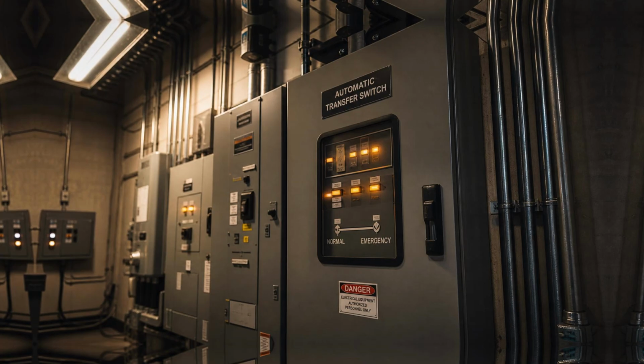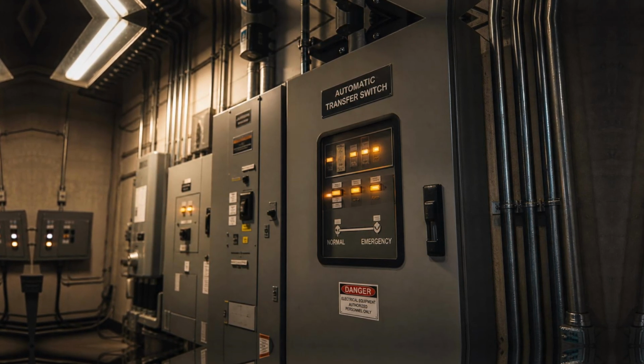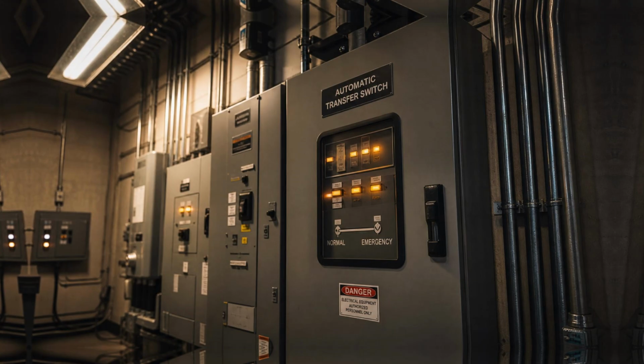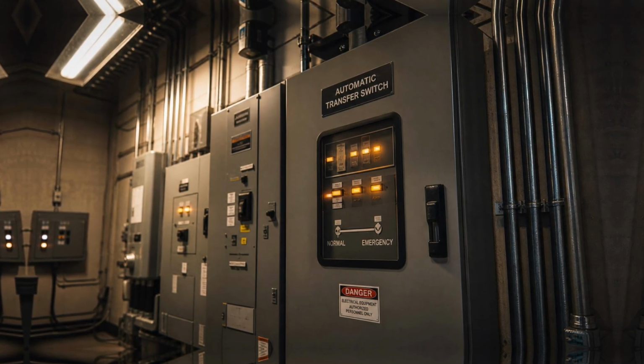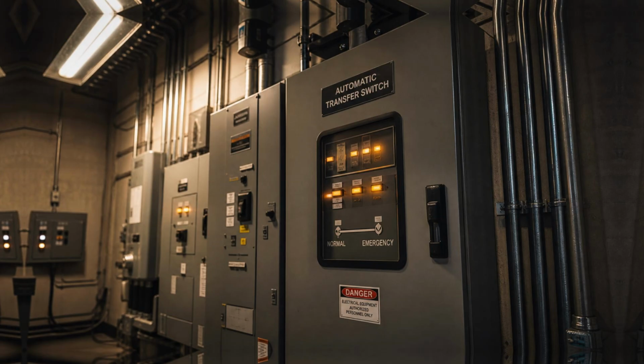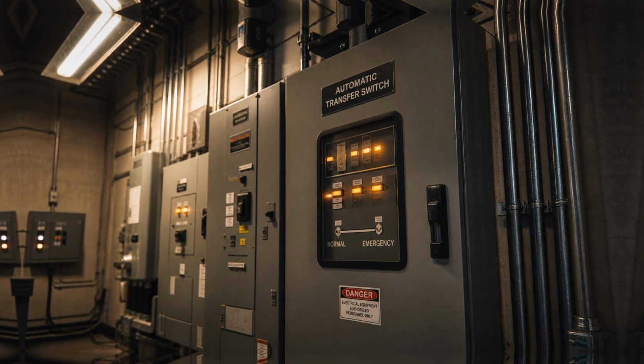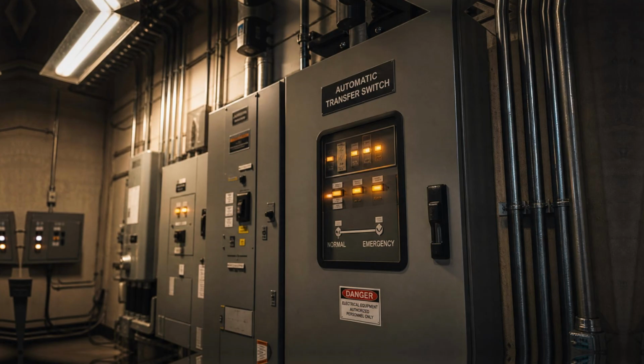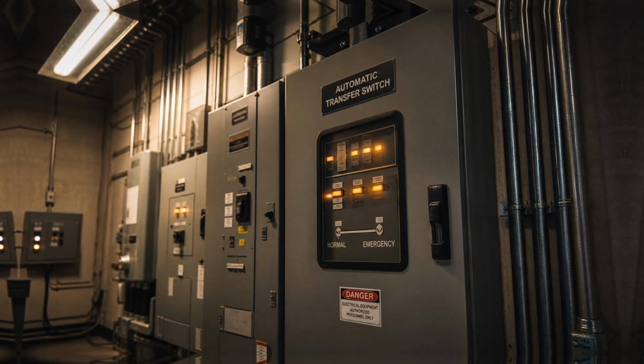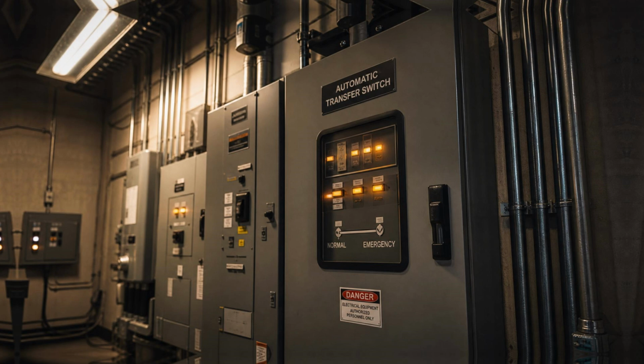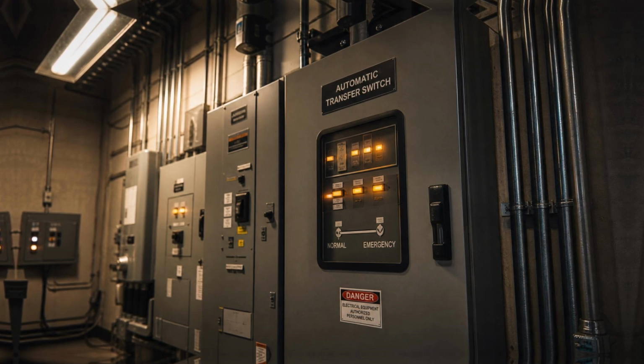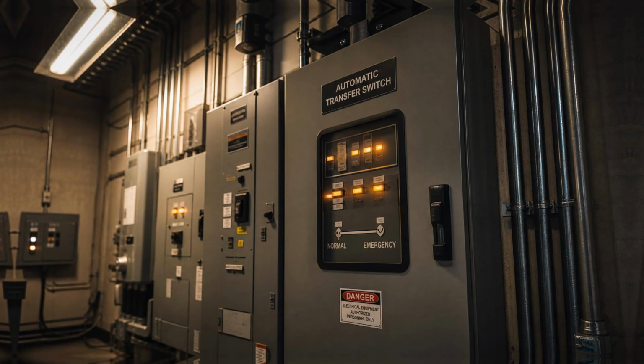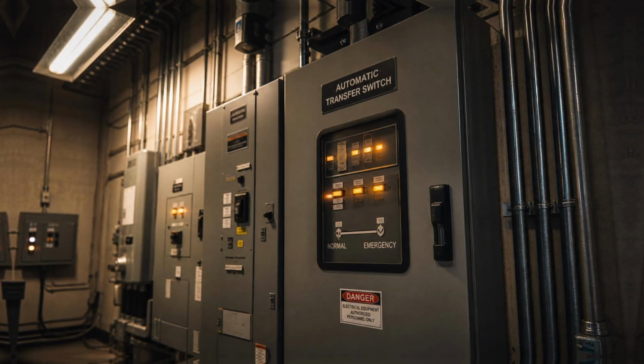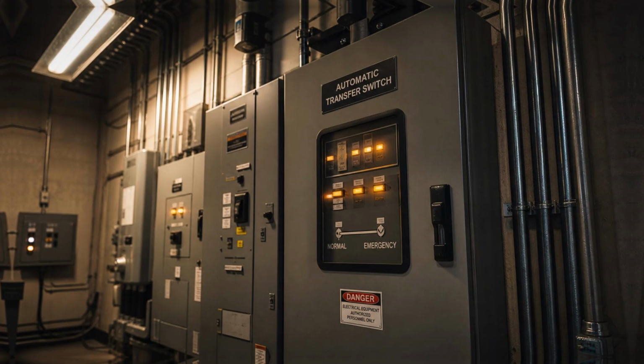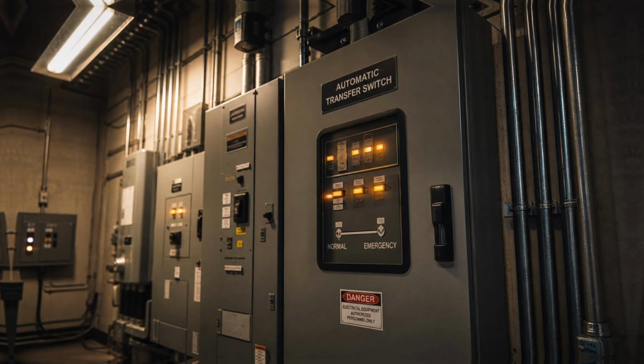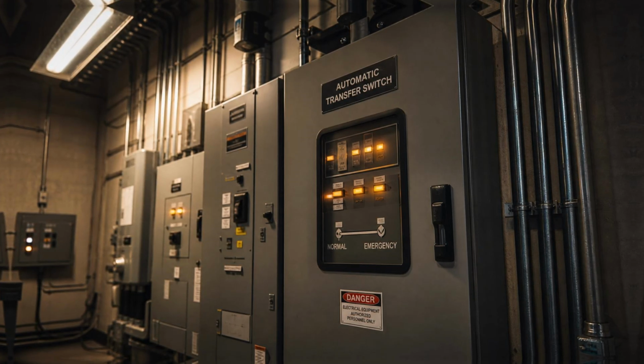The word automatic in the name is perhaps the most important word, because the great virtue of the automatic transfer switch, the reason it exists, the reason it is required in so many building types by code, is precisely that it removes human delay from the equation. Human delay, in the context of a power failure, is not a small thing. A person must notice that the power has gone out. They must locate the right equipment. They must understand what needs to be done. They must do it. And all of this, even in the most efficient and well-trained scenario, takes time.